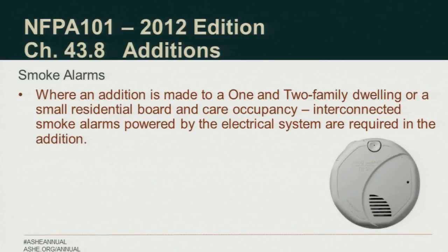Where an addition is made to a 1 or 2 family dwelling or a small residential board and care occupancy, interconnected smoke alarms powered by the electrical system are required in the addition.